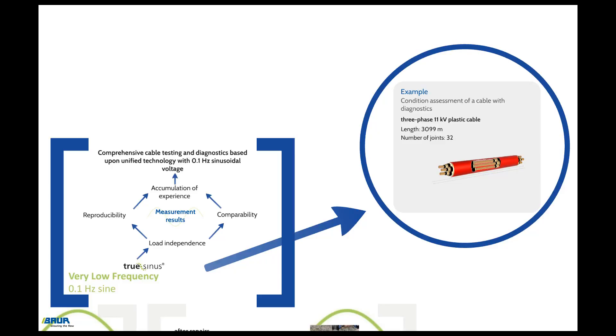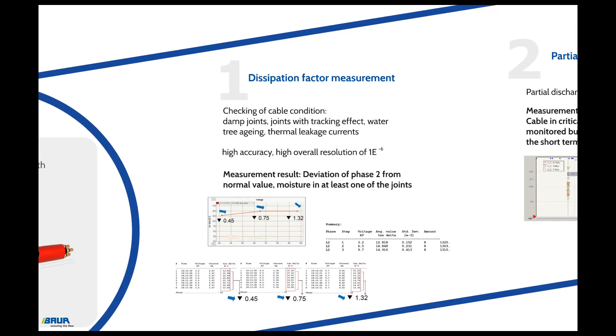The condition of a three-phase 11 kV plastic cable is to be assessed with the aid of cable diagnostics. The cable is about 3 km long and has 32 joints within this route. The dissipation factor measurement performed at the beginning supplies information on the general condition of the cable. This allows damp joints and joints subject to the tracking effect, water tree aging, or thermal leakage currents to be detected. A high level of accuracy and an overall resolution of 1×10⁻⁶ are necessary for the identification of damp joints.